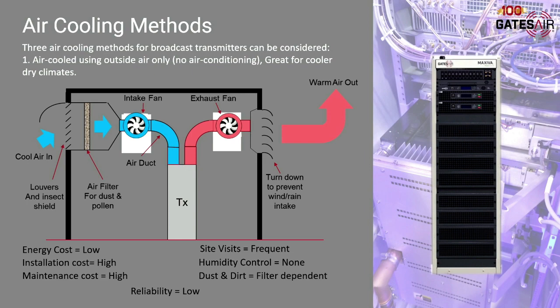So what are some methods of looking at air cooling? I can grab air from outside, bring it right into the transmitter, through the transmitter, and then blow that air back outside again. So now I reduce the heat load to my room. I don't have to have as much HVAC, right? Everybody thinks that sounds like a great idea? Well, it is, but there's always that catch. The catch is that energy costs would typically be low, but installation costs are high, because now I've got all this extra ductwork, okay?